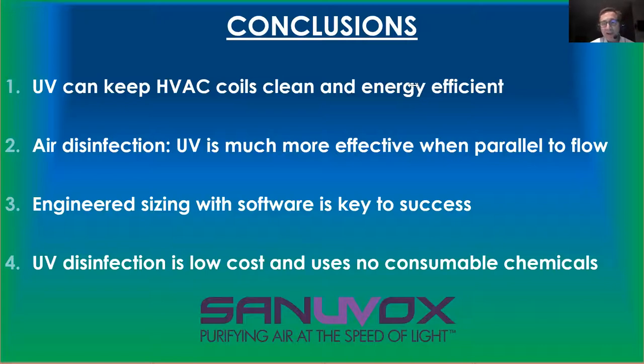And that's why when the coil is really thick and you have many fins per inch, our recommendation will be to boost the intensity on the surface from 250 to 500 if the coil is thicker. So you make sure that you get a penetration by multiple reflection that is sufficient to eliminate the toughest mold within a day, which is basically its reproduction time.